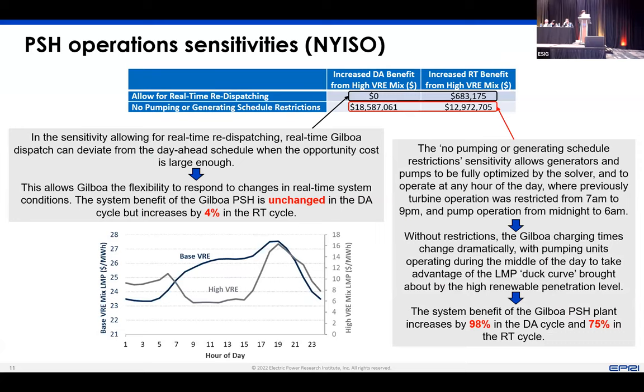The last set of sensitivities I want to share with you, again, these were run for that high renewable future. These are sort of what we call pump storage operation sensitivities. The first is around allowing for real-time redispatching. So if you remember the base case, we optimized in the day-ahead cycle and then kept that schedule fixed in the real-time. What happens if we allow the storage to deviate from that day-ahead cycle when the opportunity cost is large enough? Well, again, unsurprisingly, we did see that that extra flexibility increases the real-time benefits to the system. So in this case, about 4% in the real-time cycle.